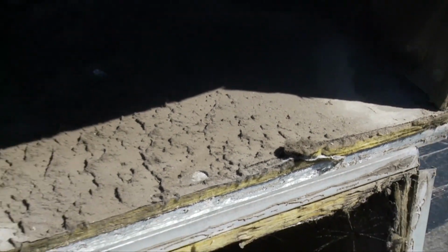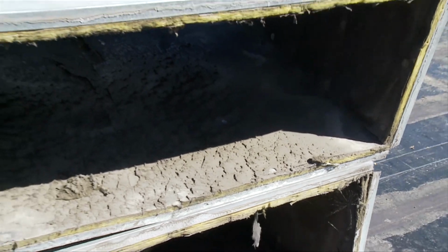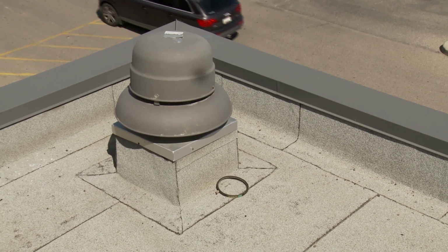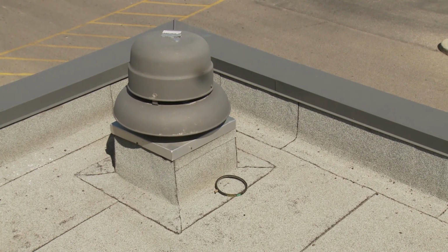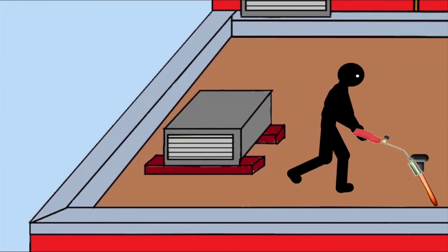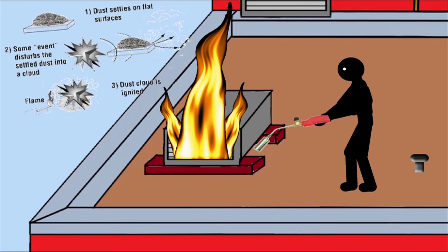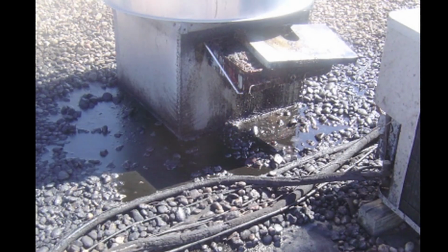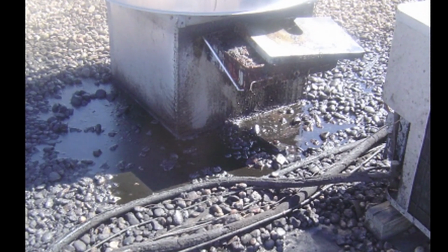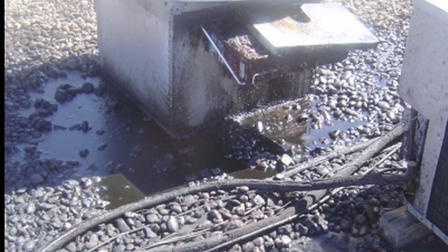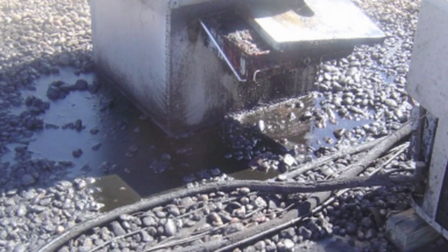Grease, lint, and dust roof accumulations. Shut down exhaust fans and clean up accumulated material under, within, and around the unit. Lint accumulations contained within and surrounding dryer vents are highly flammable as they are composed of non-synthetic fibers. On restaurants, grease accumulation at kitchen exhaust ventilators are highly flammable and need to be removed prior to torching.